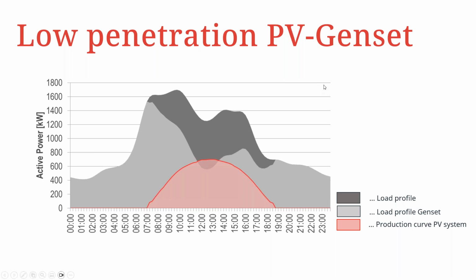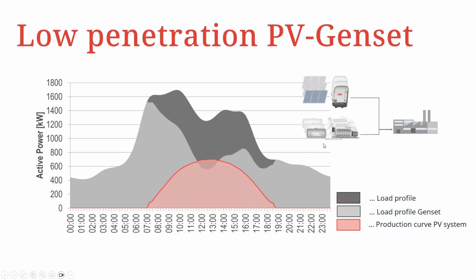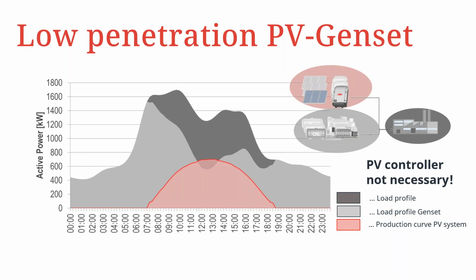Good. So having gone through the definition, let's now look at how we can actually implement this. It can come in different fashions. It can come from the low penetration perspective. With low PV penetration, it basically entails the injection of PV to complement the gensets. But in this case, the PV injection is usually low, and it doesn't really require the implementation of a PV system controller. We're talking typically from 15 to 20% of PV injection relative to the capacity of the genset. So when you have such scenarios, a PV system controller is not absolutely necessary.